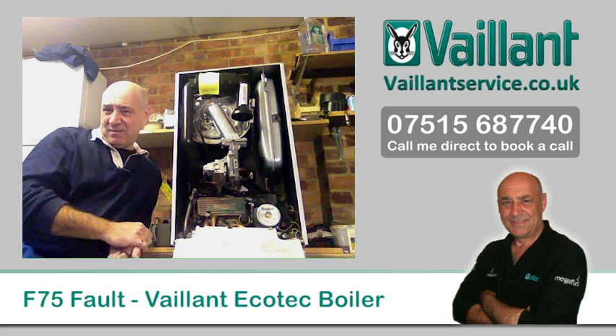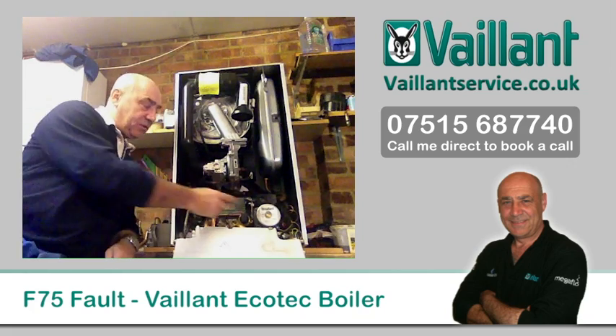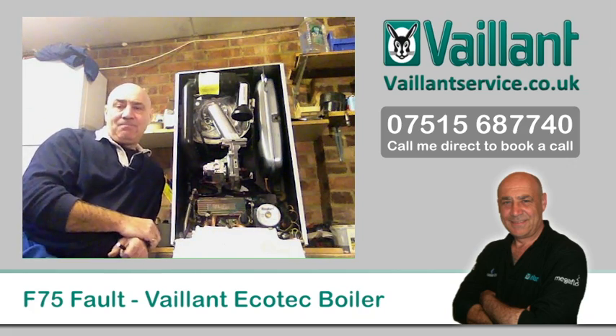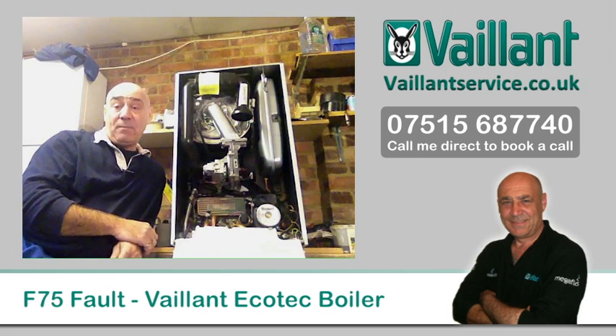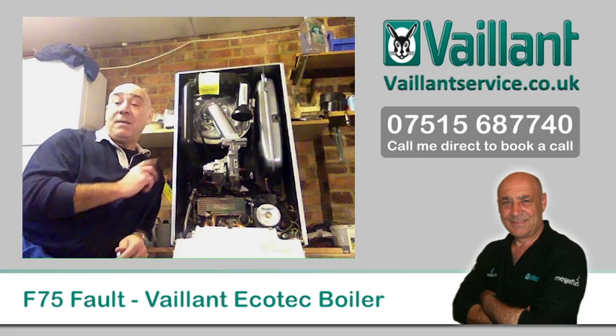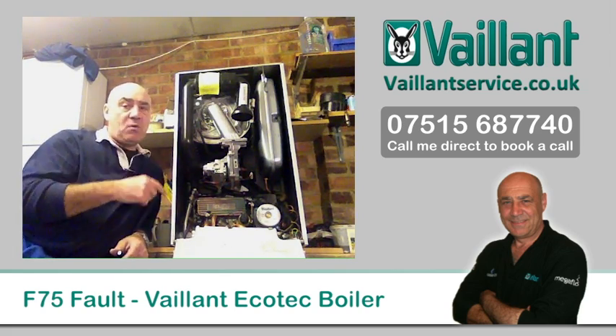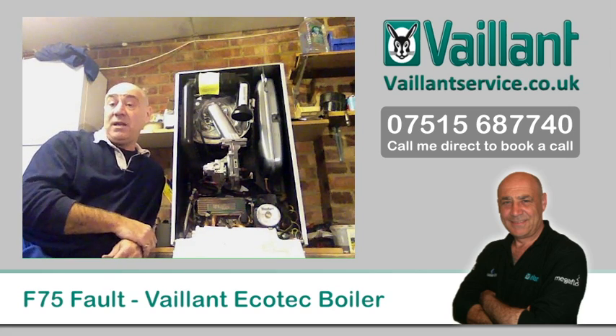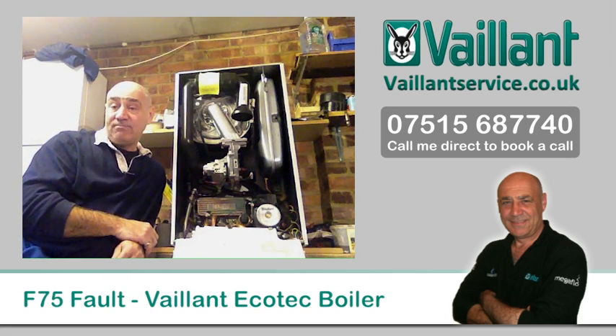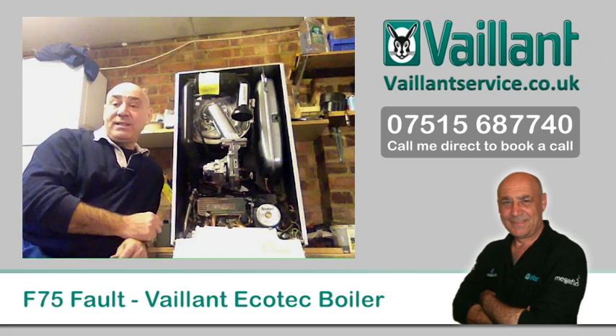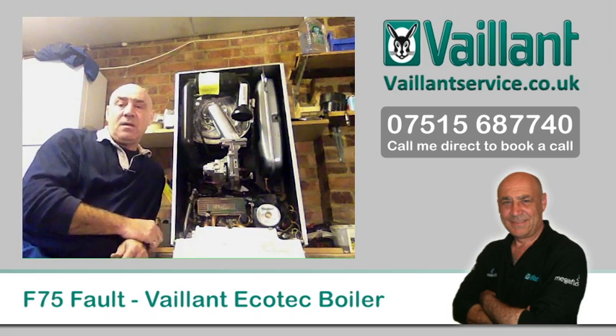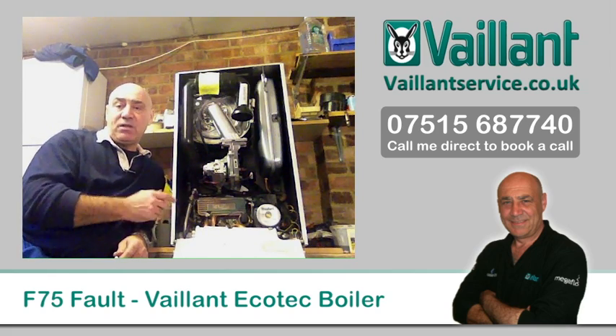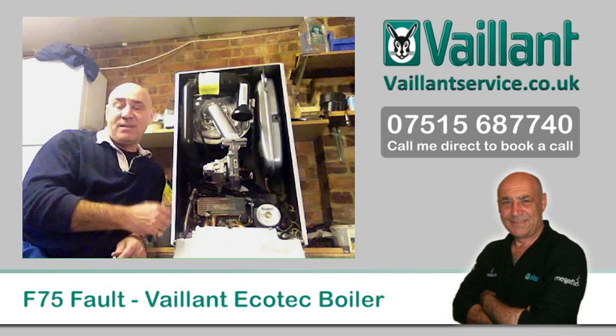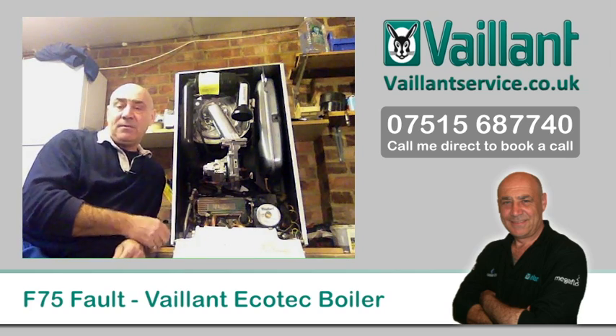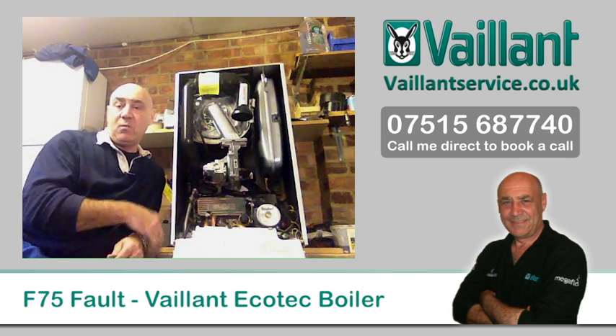So how's it going to do that then? Well, it's pretty clever really, because we have here a circulating pump. Now, the pump is a very high pressure pump, really powerful. So when that pump kicks in, water shifts around that boiler and goes out to your radiators extremely rapidly under pressure. So if that little sensor down there is reading 0.8 bar standing, when that pump kicks in, that pressure should go up a bit because the pump's running. So the sensor should then pick up an increase in the pressure inside the boiler when the pump starts.